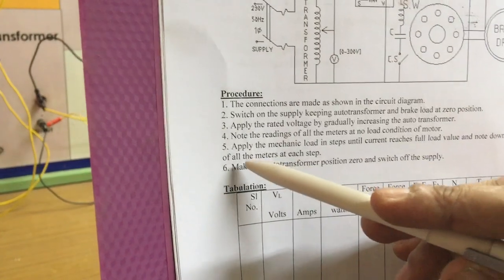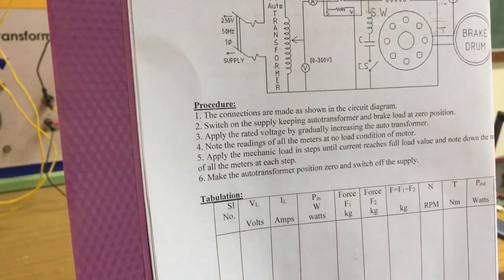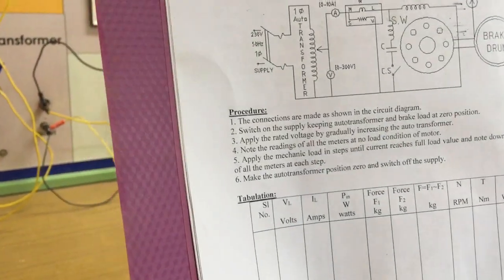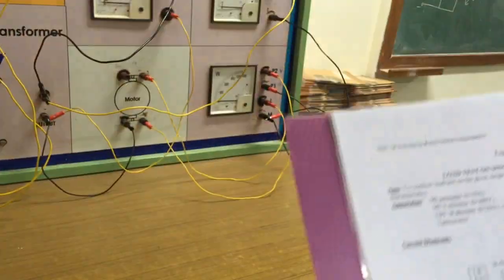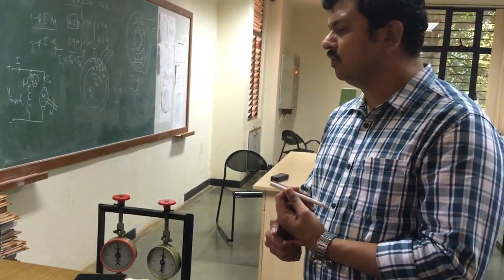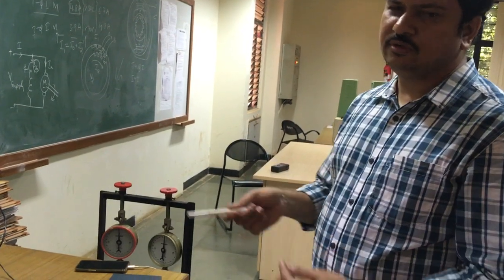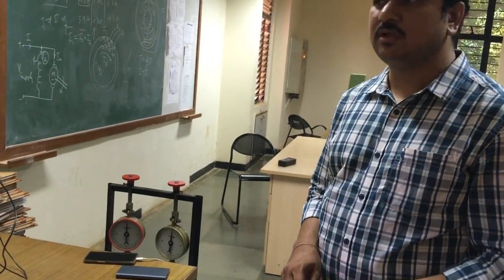Then after noting down the no load readings, apply the mechanical load or brake drum load on the brake drum gradually in steps until the rated current is reached. Once the readings are taken up to the rated current, we will release the load, make the load zero, reduce the auto transformer to zero value, then switch off the supply. So we will follow the procedure.